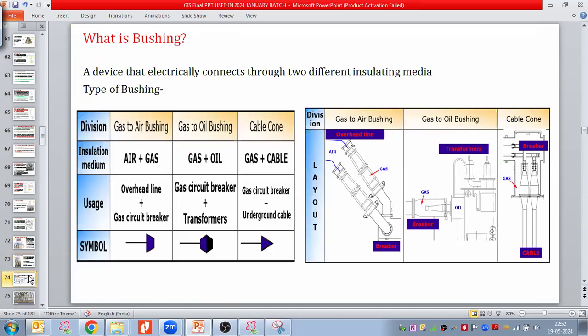Let us see what is meant by a bushing. A bushing is a device that electrically connects two different insulating media. It is connecting the gas to the air, right? It is an equipment that electrically connects through two different insulating media. Then there are the types of bushings and their symbols. It is important that when you prepare the SLD, you indicate the correct type of bushing symbol, right?